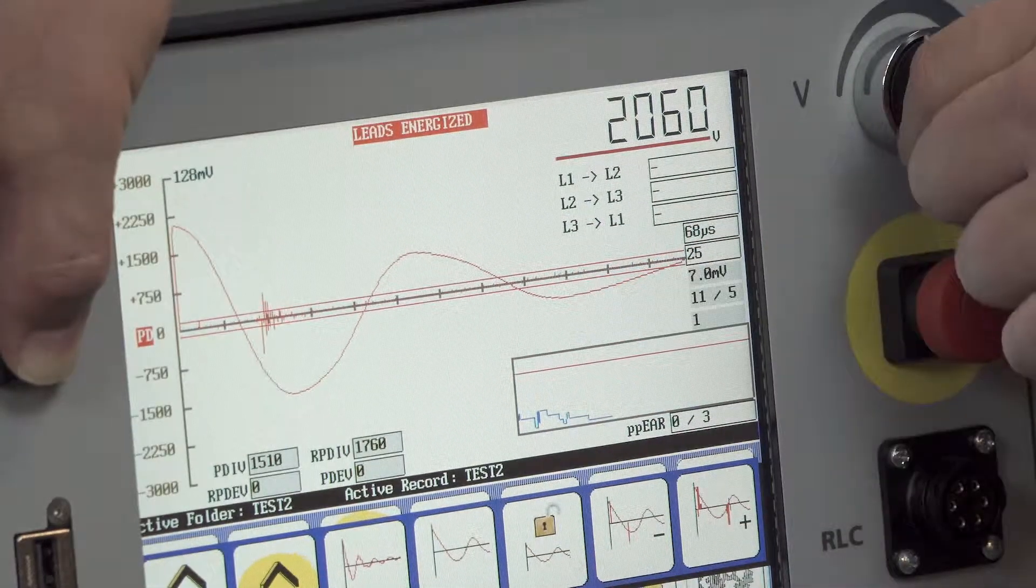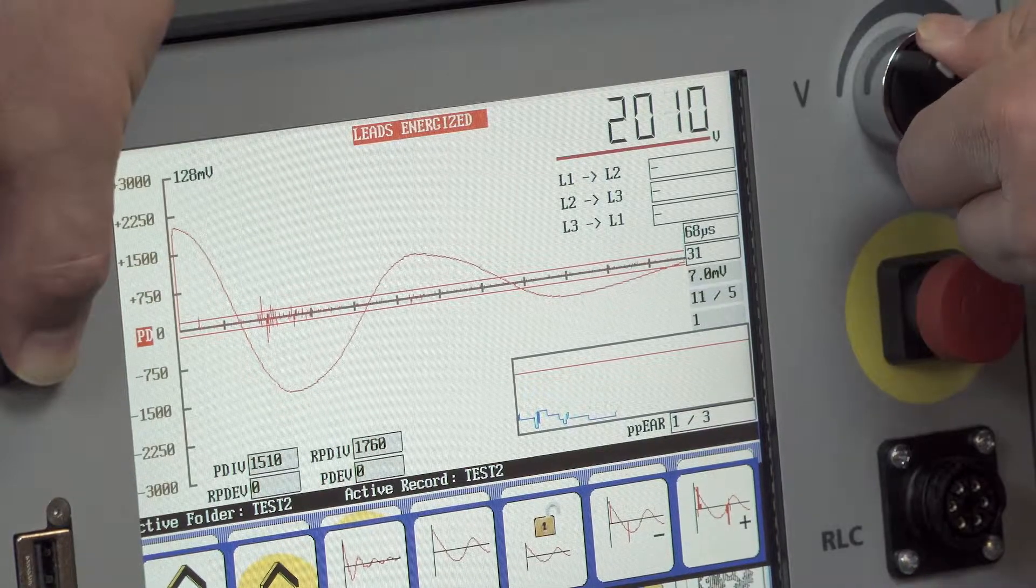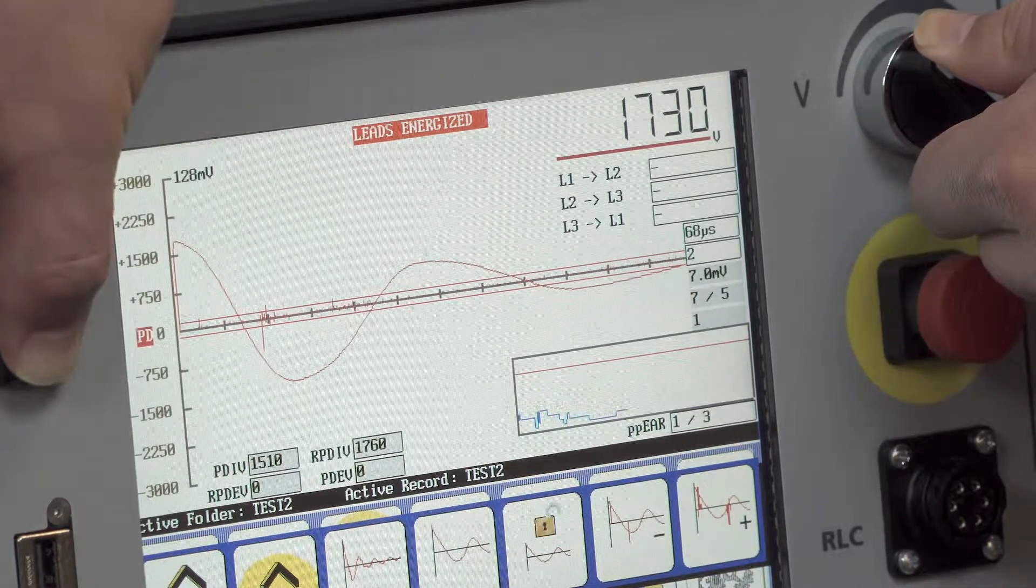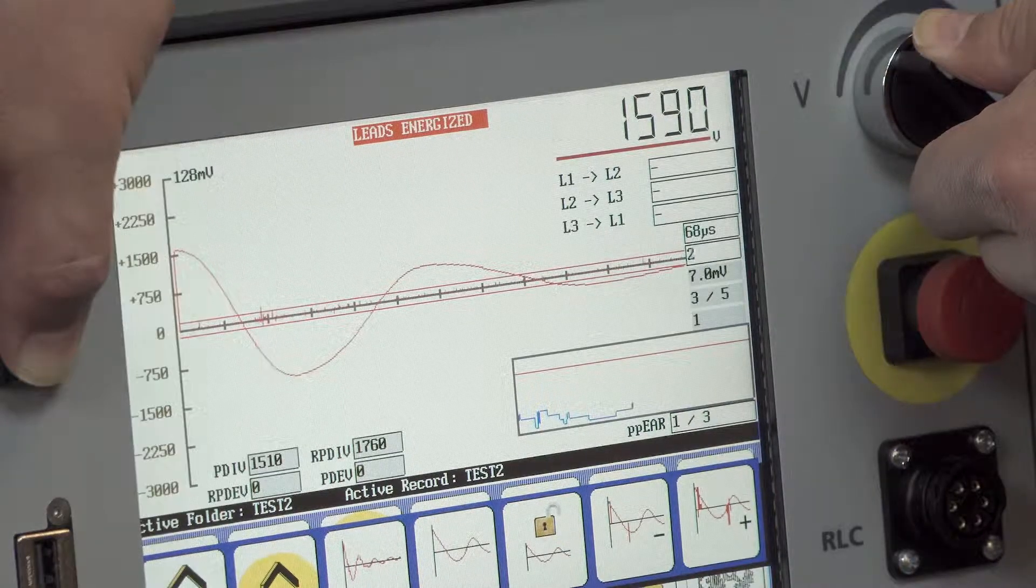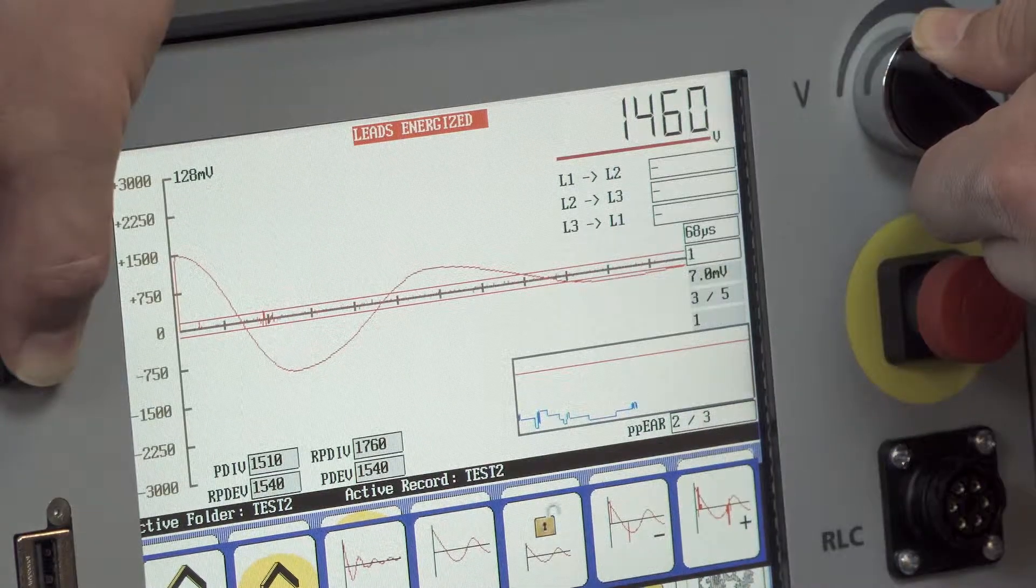Now we want to lower the voltage until the PD activity goes away. And the tester will record the partial discharge extinction voltage as well as the repetitive partial discharge extinction voltage.